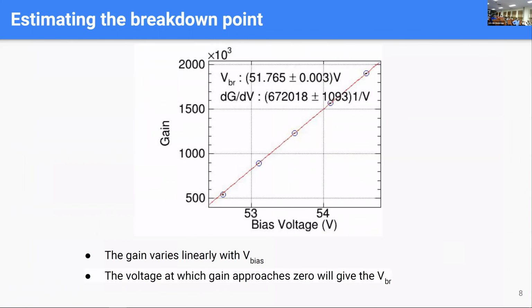What we observed is linearity, that is, all the data points fall along a line, and if we fit it with a straight line, we can calculate the breakdown voltage and the slope. Basically, the point where the straight line meets 0 on the y-axis is our breakdown voltage, because this device is made to operate over the breakdown voltage. That's why, when the gain is 0, that is our breakdown voltage.